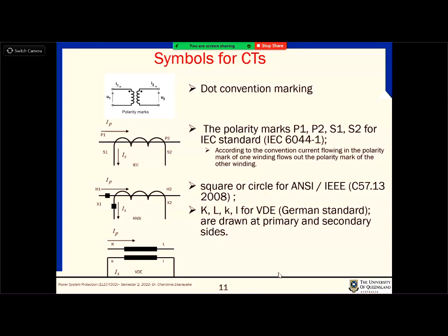Symbols for CTs in a real calculation, there are many different symbols used. This is the dot convention marking that we usually use, but if you look at different standards, they have different symbols depending on the countries. IEC does not mark it with the dot, they mark the direction of the current flows. These two currents will have the same phase, that is IEC. And then the IEEE, which is the US one, marks it this way, right? You have this dot, but also IP and IS directions.